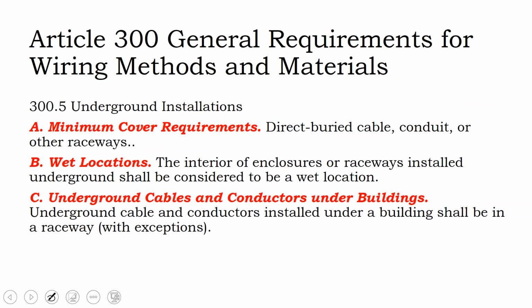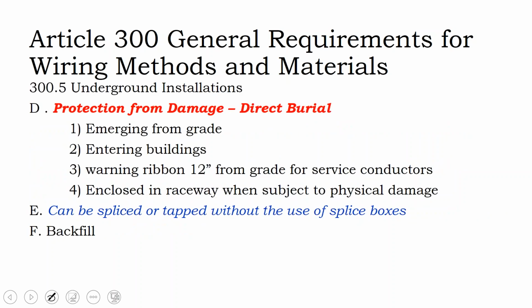The conduit in a direct burial wire run is mainly there for protection. It's not there to put in a pathway that you can just use over and over again if you ever want to add new circuits or upsize your wires in the future. Generally, you put in empty conduits for future expansion if that's something that you want to do. Now, if you're doing a true direct burial wire run, so we do direct burial wire runs in Mississippi where we don't get rock and boulder in our dirt. You're either in good planting dirt that's incredibly sandy and clayey, or you're in a rock concrete, completely uniform shelf. You know, we're not a very interesting geography, I'd say.